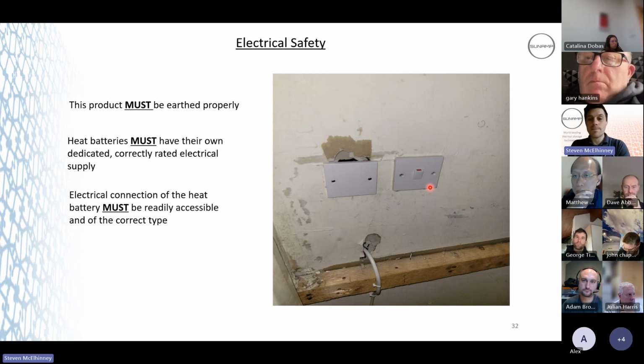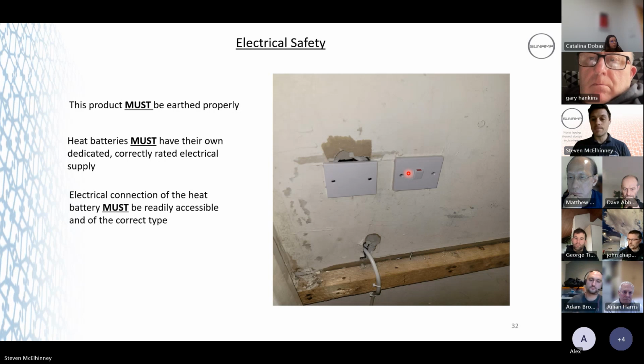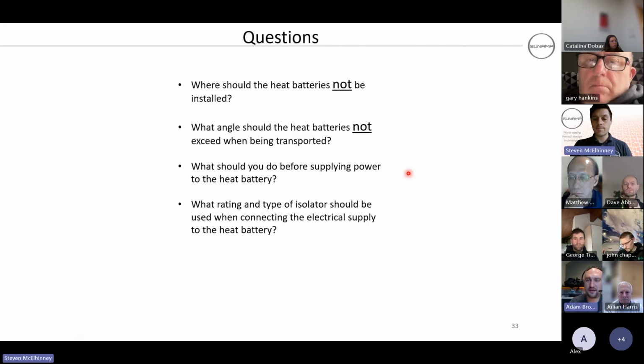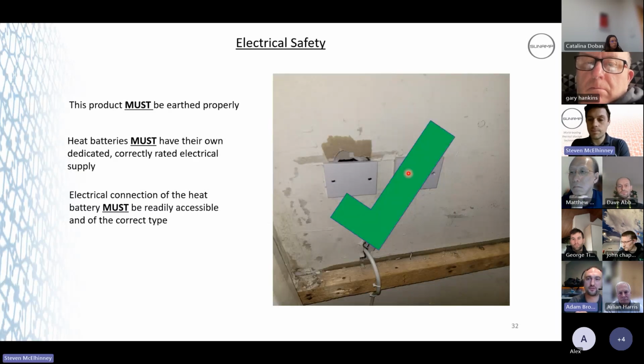That's what we'd recommend. When you're talking about the eddies and stuff for the ePVs, Alex, it's a double pole isolator that will feed. If you think about your flow chart, it'll be double pole isolator, eddy, then your heat battery. So that one isolator isolates the eddy and the heat battery at the same time. All right. Just got one with the electronic limescale reducer, does the same apply with that? So you've got your 20 amp double pole switch, and you can take something off that to feed the live for the descaler. The descaler, you could just plug into the ring main circuit, Adam.